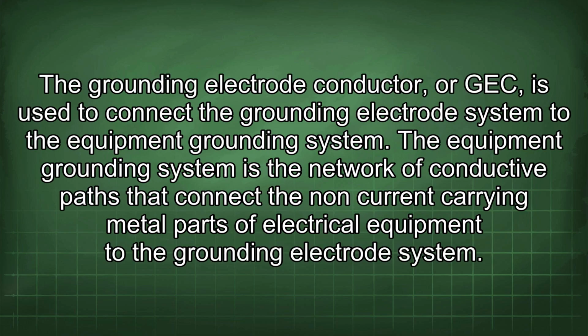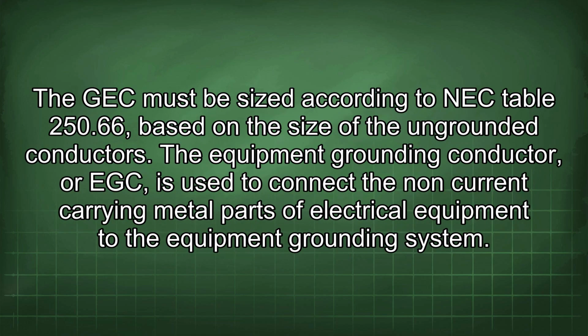The grounding electrode conductor, or GEC, is used to connect the grounding electrode system to the equipment grounding system. The equipment grounding system is the network of conductive paths that connect the non-current carrying metal parts of electrical equipment to the grounding electrode system. The GEC must be sized according to NEC Table 250.66, based on the size of the ungrounded conductors.